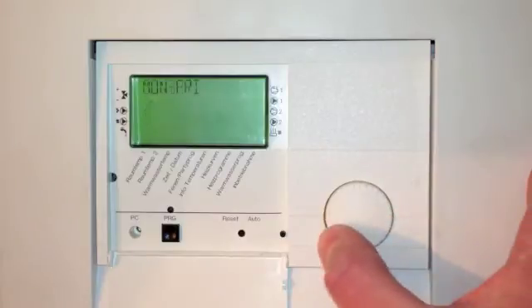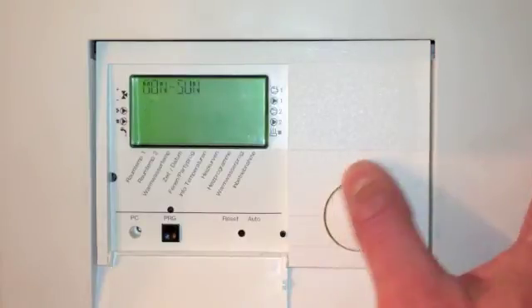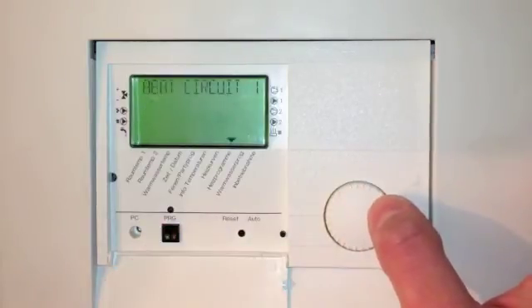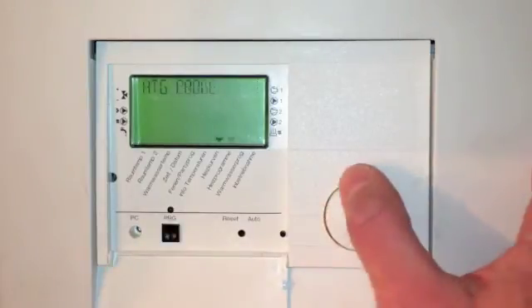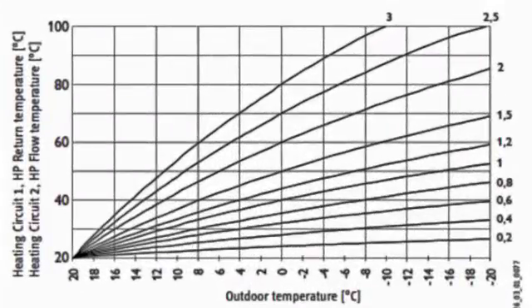If you keep scrolling and pressing back, you will get back to the main menu. Now I'll explain weather compensation and the heating curve. The heat curve alters the water temperature in the buffer tank for your underfloor heating or radiators depending on the outside air temperature.